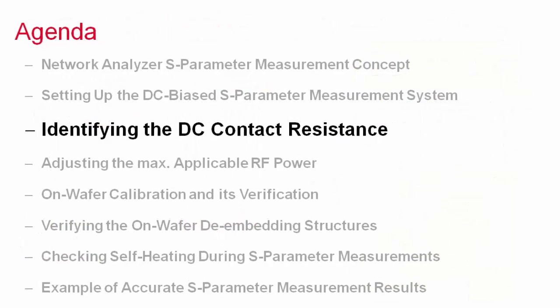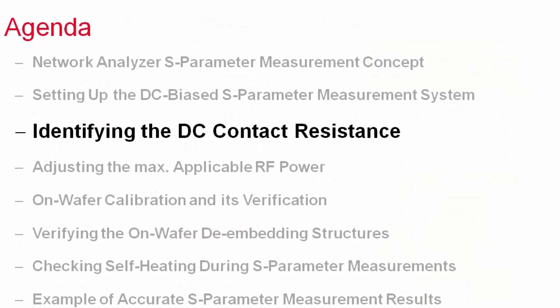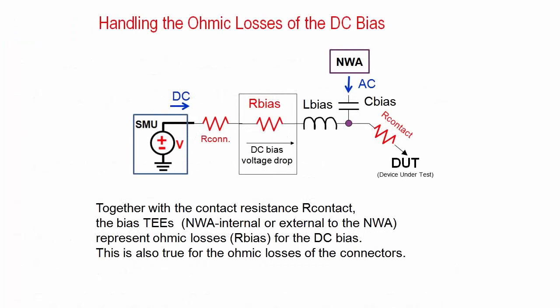We are now ready to go step by step through the preparations of the S-parameter measurements. We first determine the ohmic losses of the DC bias path, represented by the connector and cable losses, the loss in the bias tees where DC and RF signal are combined, and the on-wafer contact resistance.